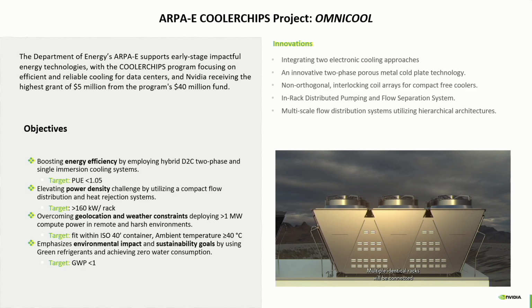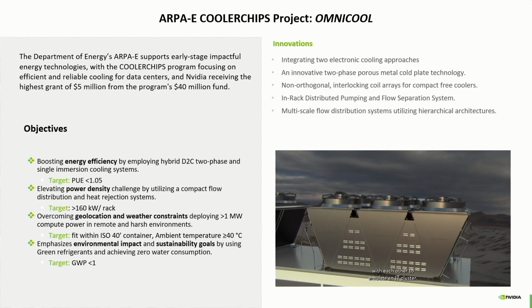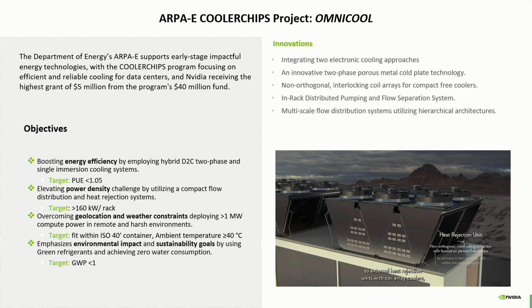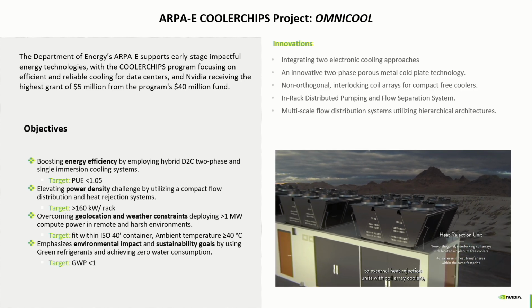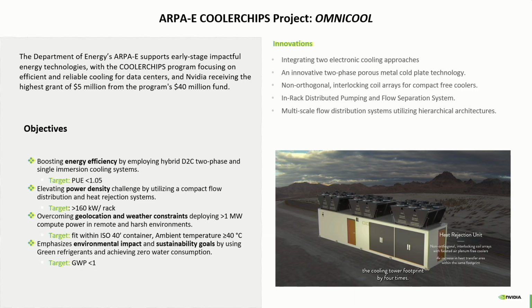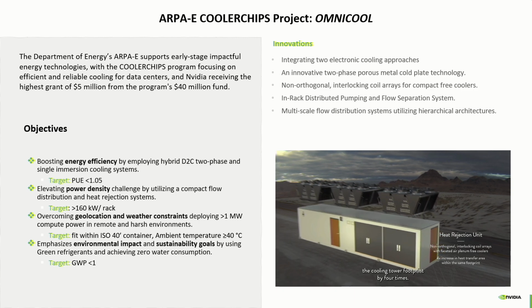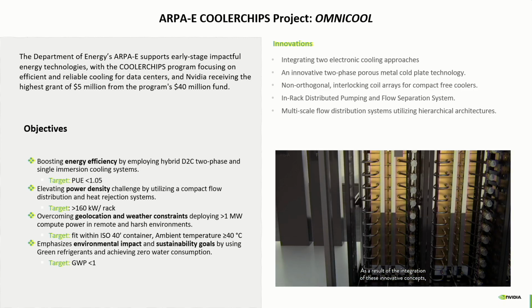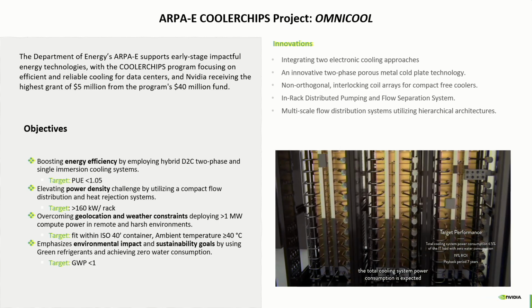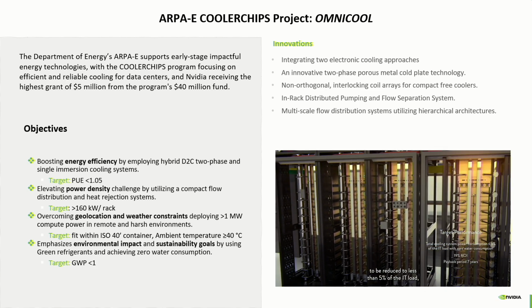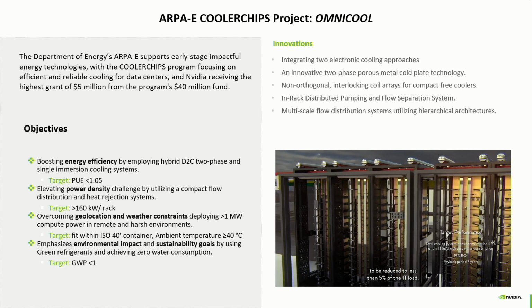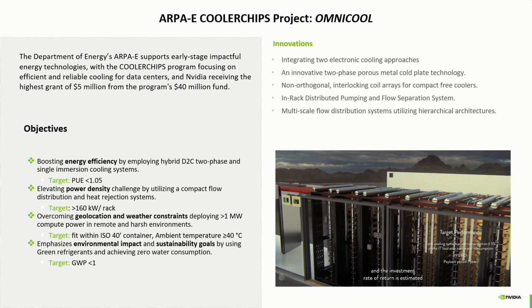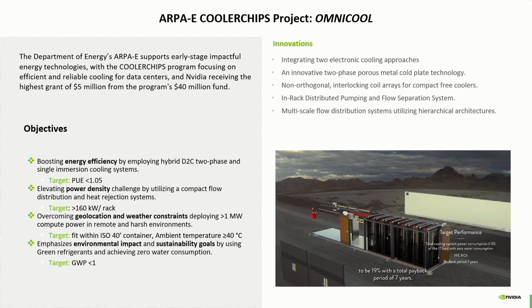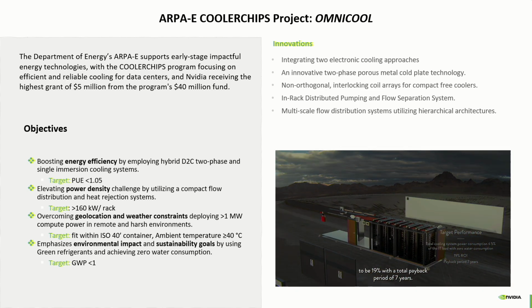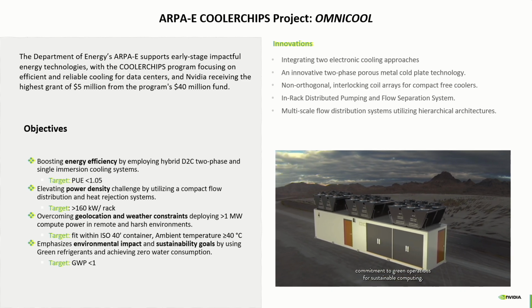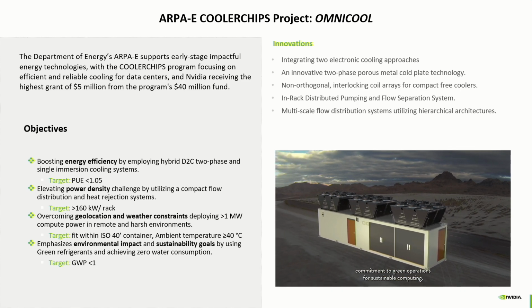Multiple identical racks will be connected with each other to emulate an IT cluster. All the racks will be connected to external heat rejection units with coil array coolers, which can potentially reduce the cooling tower footprint by 4 times. As a result of the integration of these innovative concepts, the total cooling system power consumption is expected to be reduced to less than 5% of the IT load, and the investment rate of return is estimated to be 19% with a total payback period of 7 years. This technology will strengthen our team's commitment to green operations for sustainable computing.